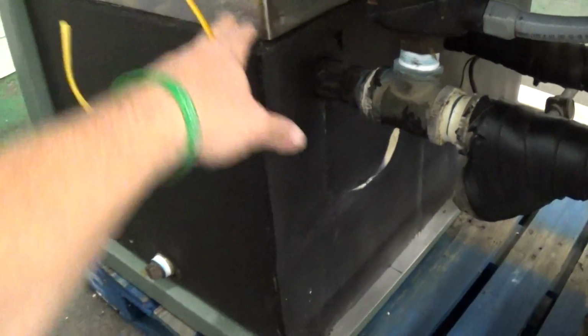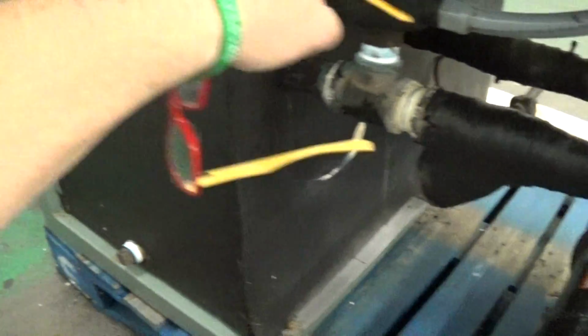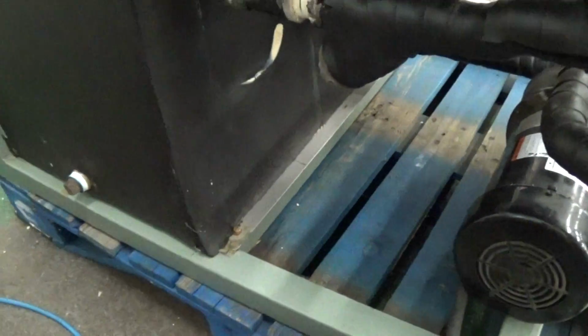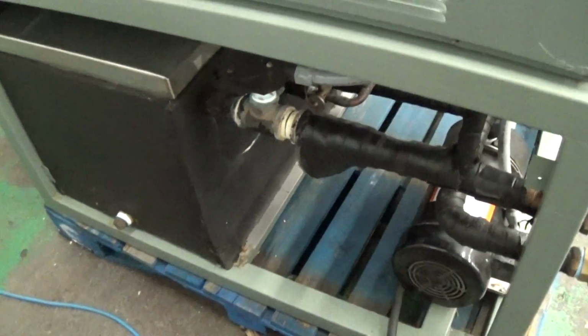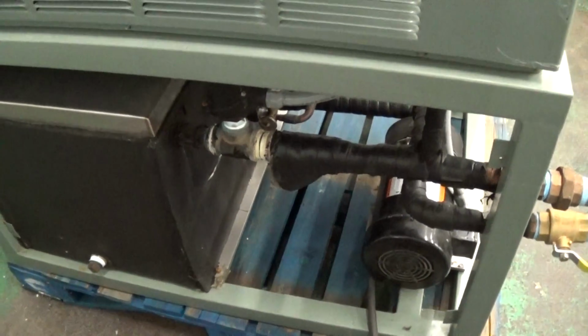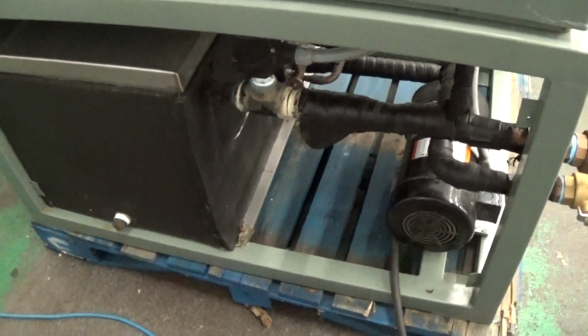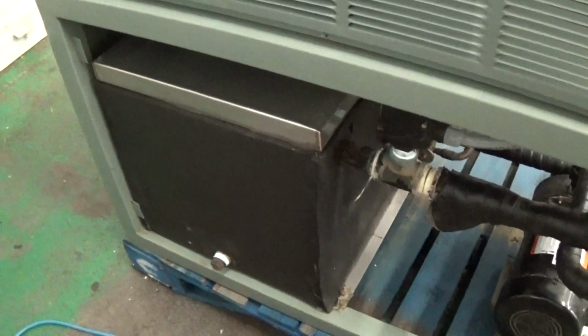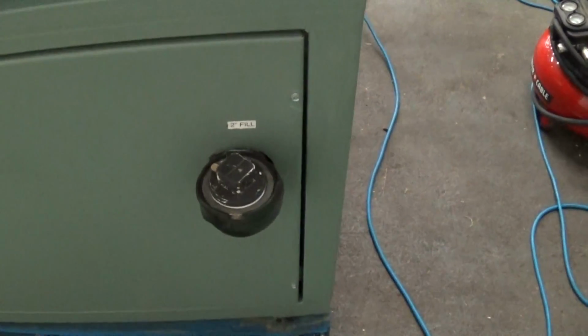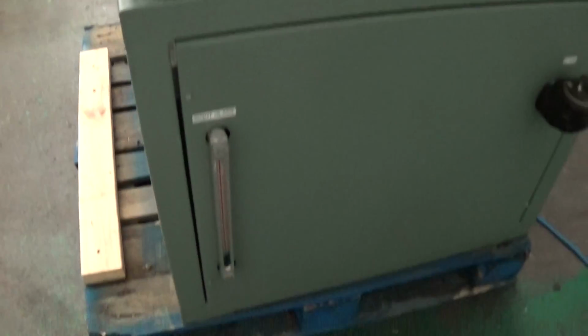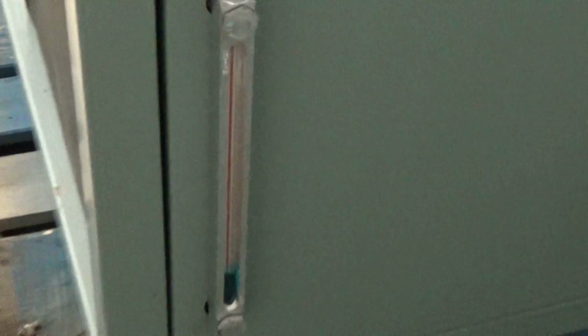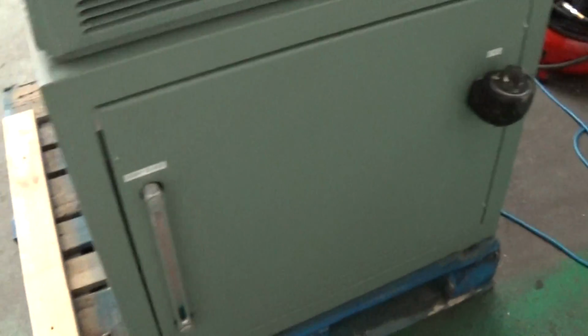We have an insulated stainless tank here. You have a drain. Again, this unit has the cover option, so all the covers will ship out with all the covers on all 3 sides. If it was us during startup, we just have the covers off for the first day or two, so everything's hunky-dory. You know, check the tank level a couple times. You do have a fill here, and you do also have this sight glass for the tank level. In this case, the way it's set up, we just put in some high concentration glycol. We probably have it like a 5th full just for this particular test. But you bring it right up to the top.